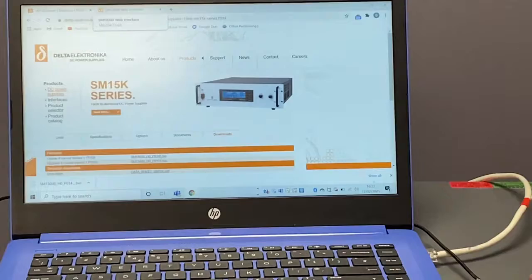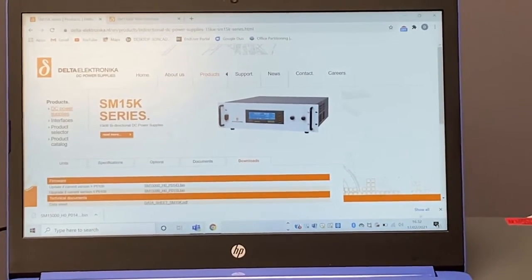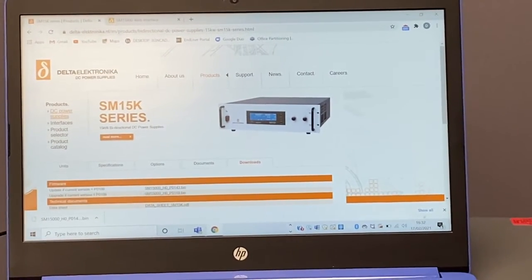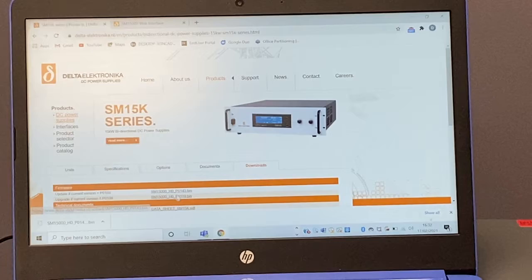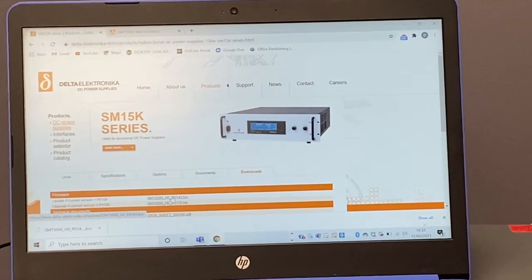Then we go to the Delta Elektronika website and select the model that we're updating. Under downloads you'll be able to see the firmwares that are available. Pay particular attention here because there are at least two different versions. You need to select the correct one depending on the firmware that you're updating. For us we're selecting the top unit.